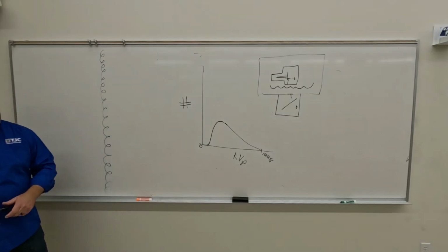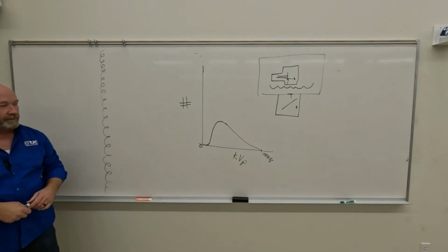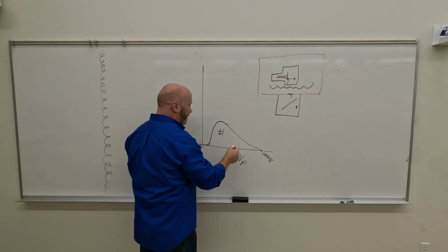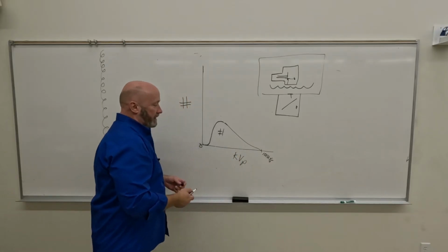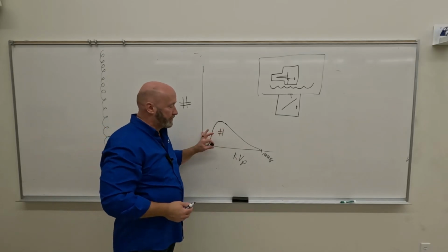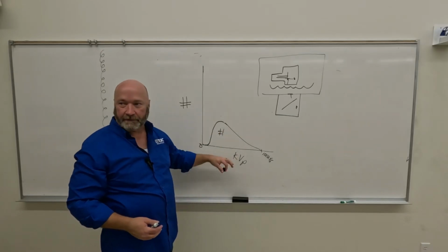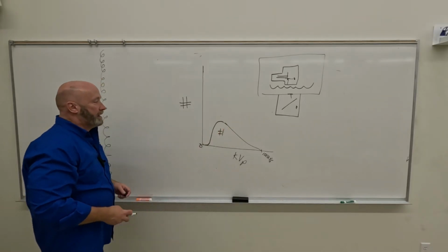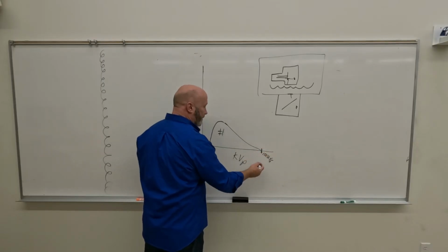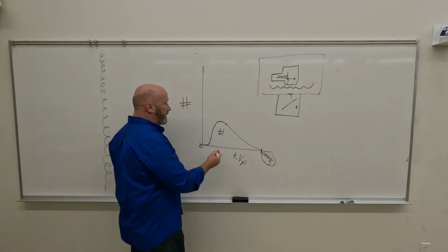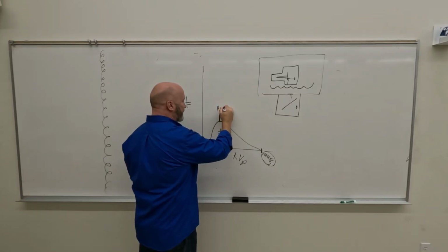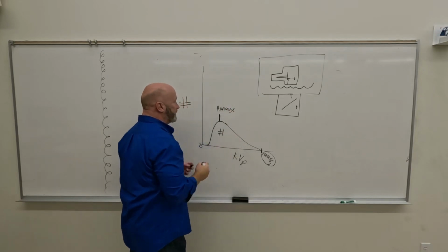Okay? There are a couple of things that bear explanation. So you set a technique, and this is going to represent the number of photons that you create. Again, in this example, I didn't want you to equate that with mAs, because we're going to take a look at what happens to this thing as we increase or decrease mAs. So the parts of the brems spectrum: we've got this toe out here that represents the highest energy that you can create. We've got the very highest point right here, which should represent the average energy that we create.